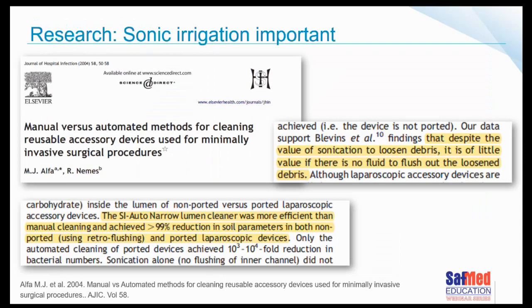Here is some published research. What they did was take a whole set of laparoscopic instruments and inoculate them with a test soil, and that test soil actually included some bacteria. They then cleaned the instrumentation in an ultrasonic cleaner with a lumen flush, and they cleaned some manually. And the ones that they cleaned manually, they just used a syringe to flush with. Their findings were that the automated method was more effective to clean with versus the manual method, so obviously ultrasonics, and that the ultrasonic cleaner was the only method that reduced the bacterial count by a log of 10 to the power of 4. So one can conclude then that in this case, cleaning lumen instruments with ultrasonic cleaning is going to be far more beneficial.